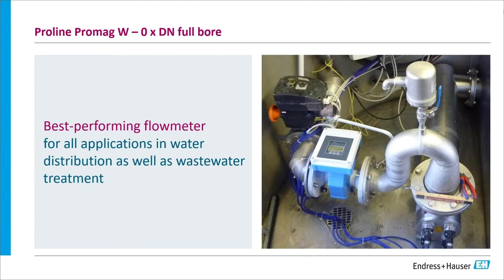So this zero straight run unrestricted flow design solves this problem. If you look at the picture here, it's a very tight installation, has a 90-degree bend coming in and out of the meter. And on this installation, we have no loss of accuracy at the meter. So it's a very good technology advance for flow metering.